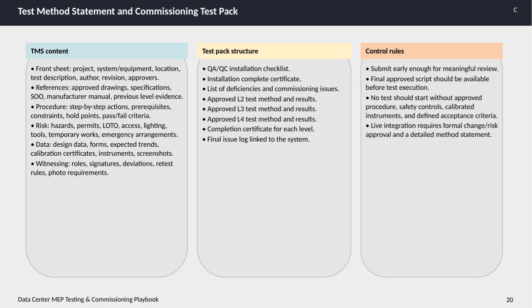Moving on to the test pack structure, this acts like a comprehensive folder that tracks quality and progress throughout commissioning. It contains a QA/QC installation checklist, installation completion certificates, and a detailed list of any deficiencies or commissioning issues discovered. It also includes the approved test methods and results for levels 2, 3, and 4, demonstrating the progression and thoroughness of testing at various stages. Completion certificates for each level close out those stages formally, while the final issue log links all relevant information back to the system, ensuring everything is traceable.